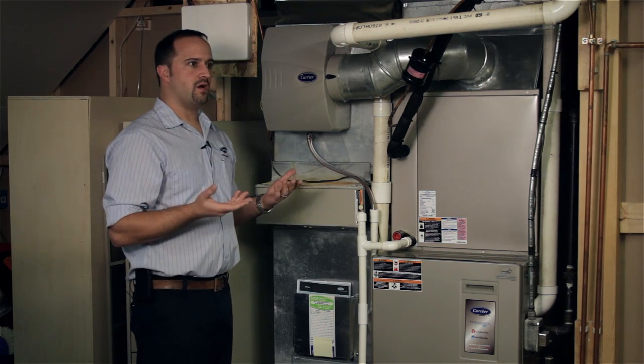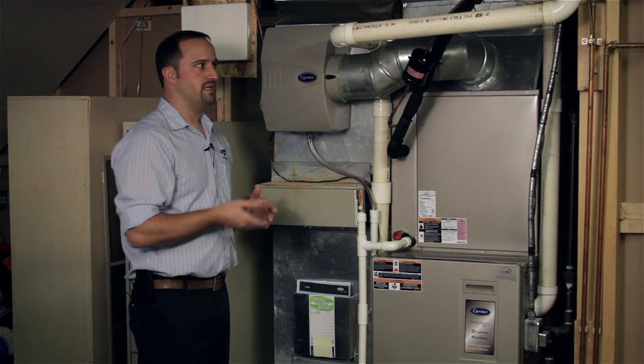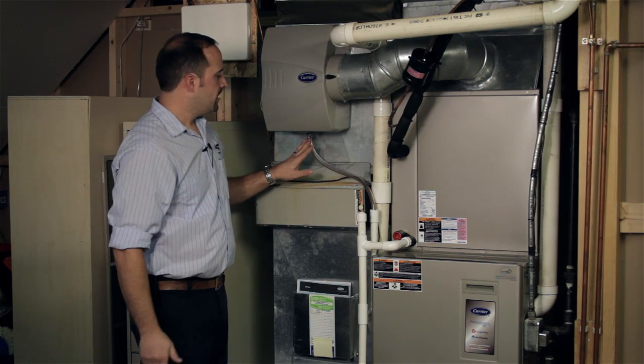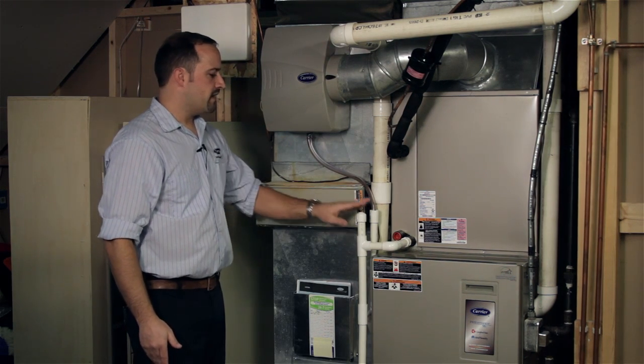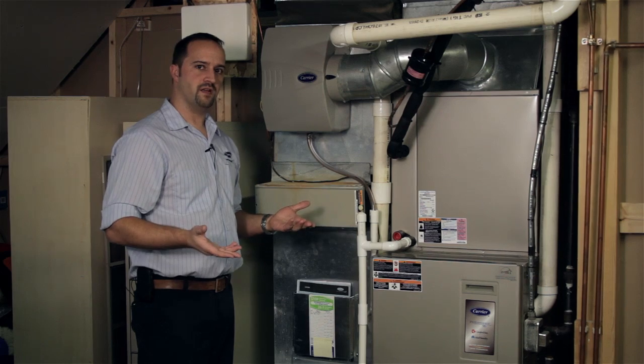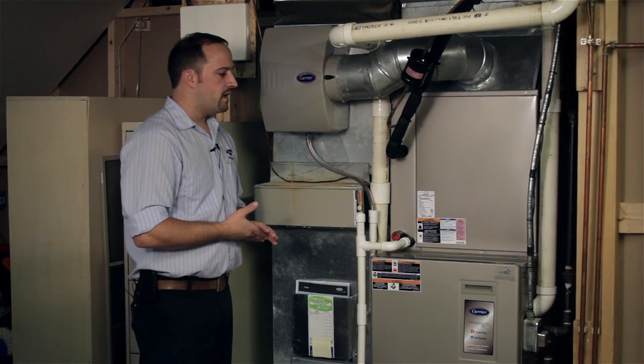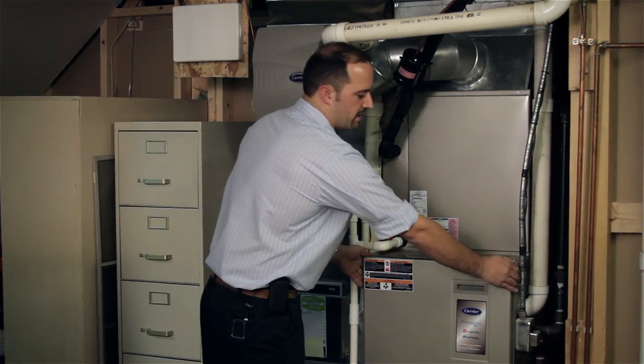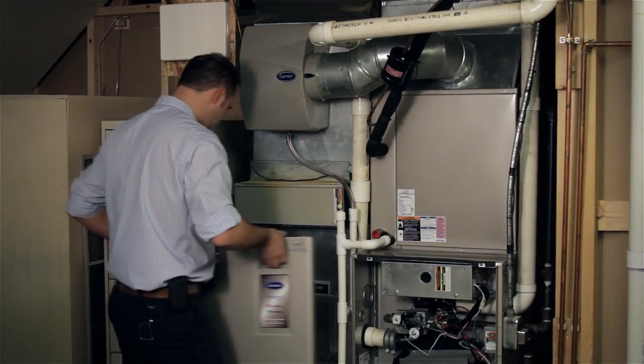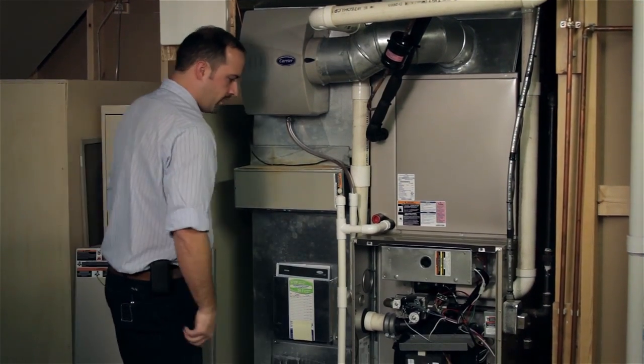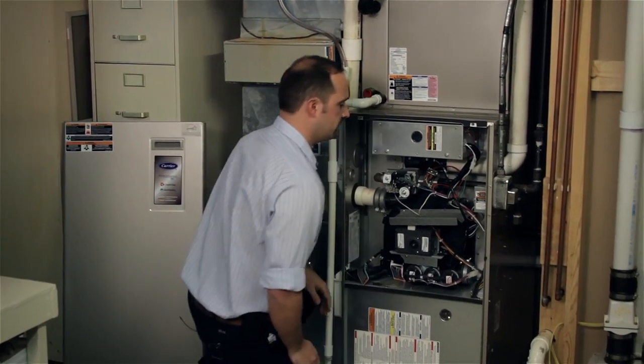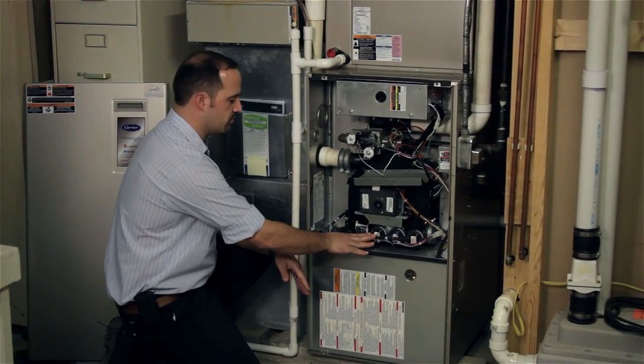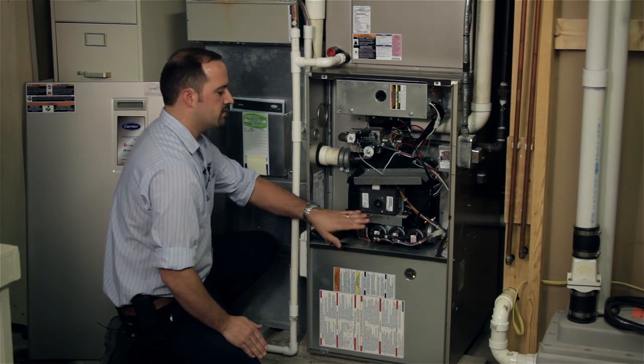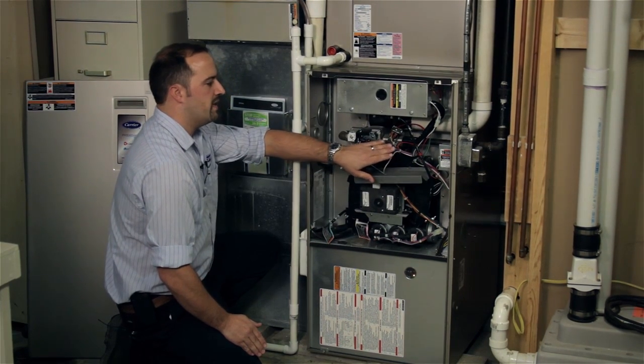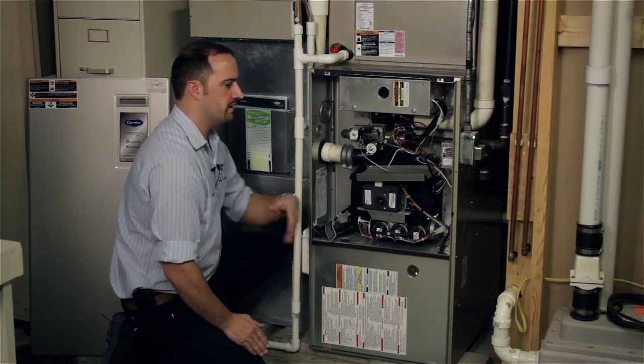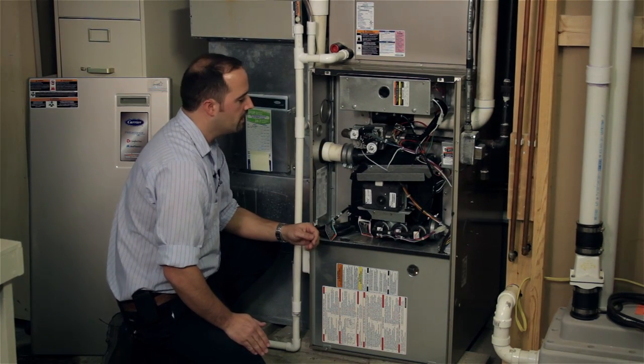He's going to just do an overall observation of what's going on with the system, make sure there's no leaks in the vent pipes and the drains for the humidifier or the condensate, just an overall assessment of how the system is doing. He's going to go ahead and pop off the front panel to the equipment. And inside here, he's going to be checking the overall cleanliness, the condition of the rubber hoses, the condition of the motors, the wire connections, making sure nothing's rubbing up against anything sharp where it could get a short circuit or something of that nature.